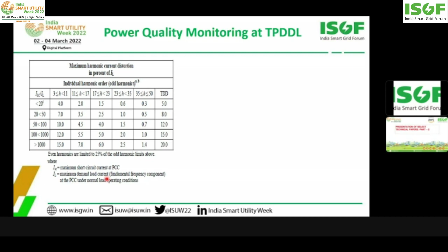Now, before entering into the next slide, I would like to explain a little bit about current harmonics. There are 2 parameters which can explain current harmonics. One is the THDI, which is total harmonic distortion of current, and TDD, which is total demand distortion.